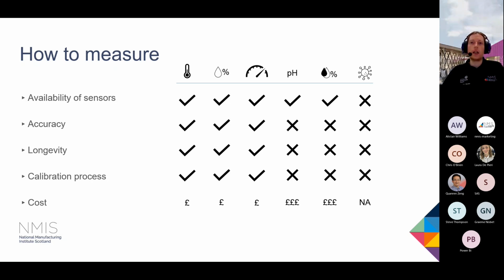For the level, that's something that could potentially be a challenge. In our case, we were lucky that our machine has a float on it—a little yellow piece of plastic that moves up and down on a linear rail or linear slider. All we had to do was put a distance sensor below that to see how far away the float was, which allowed us to calibrate and get a pretty good measurement of the level on the machine.